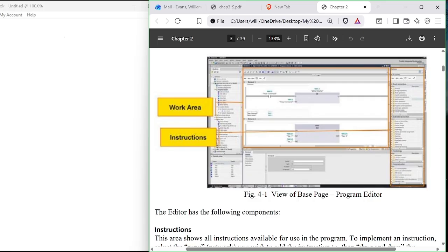So you start putting more, and you look at my programs. I put a lot of stuff in each rung, or in each network. On each page, in other words, a network is like a page. And you'll see that I'll start, and then I'll make another little, what I call a sprig or a little jumper down, and then I'll do another one. You look at my program and say, why is he doing that? Because it works. And you can see more on the screen at one time. Why is that important? You're troubleshooting, and you don't have to keep scrolling up and down.